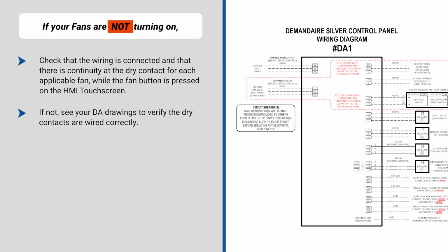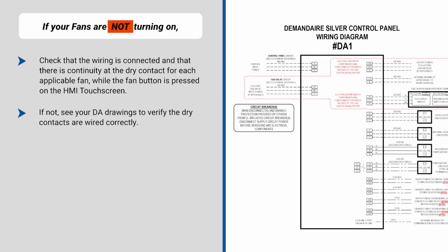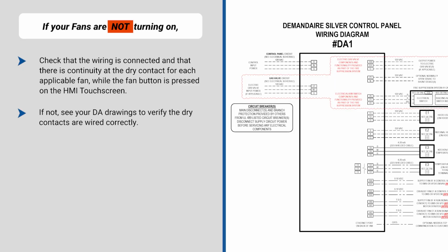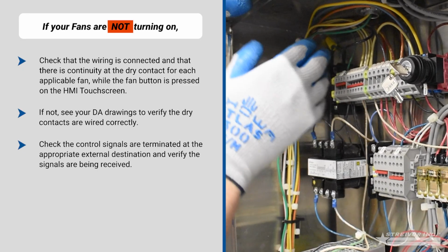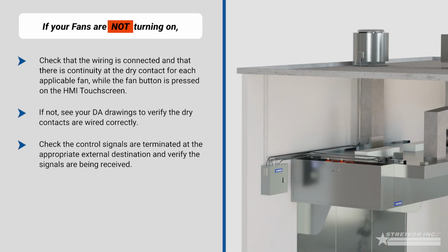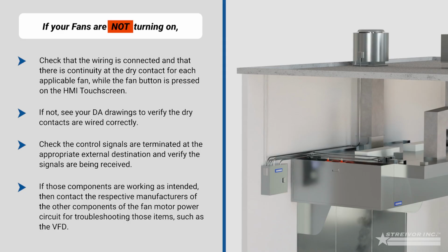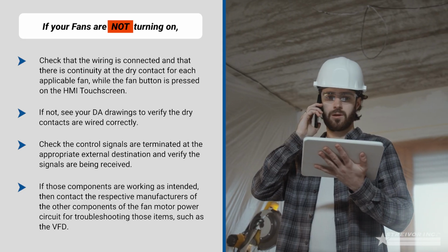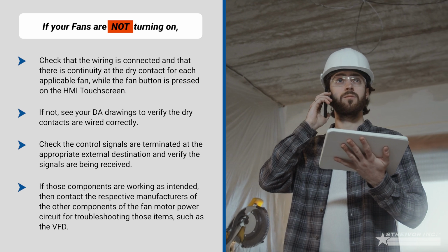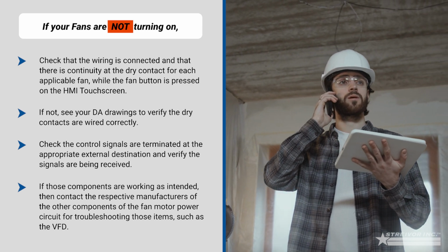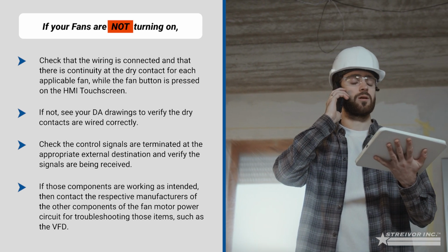If not, see your DA drawings to verify the dry contacts are wired correctly. Check the control signals are terminated at the appropriate external destination and verify the signals are being received. If those components are working as intended, then contact the respective manufacturers of the other components of the fan motor power circuit for troubleshooting those items, such as the VFD.